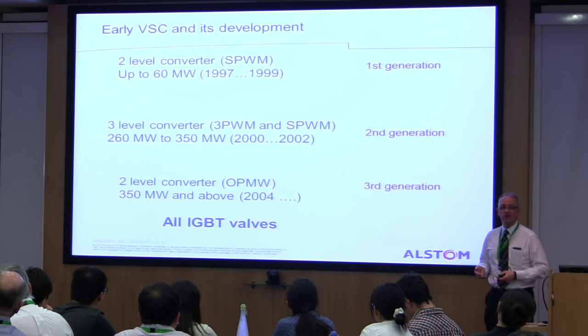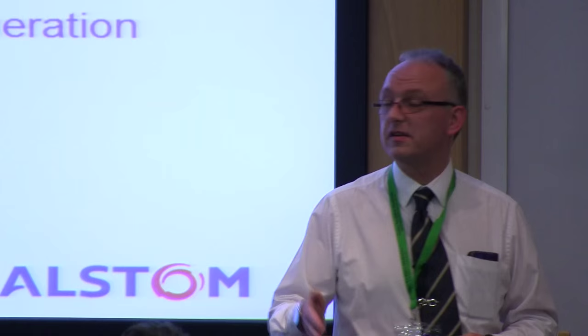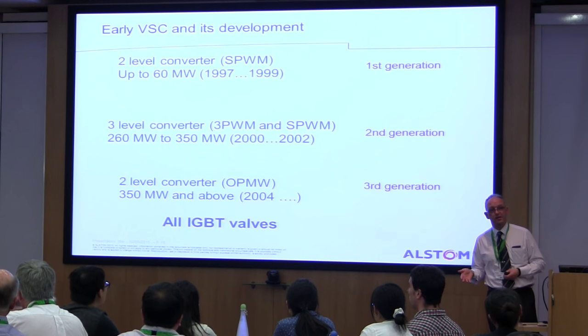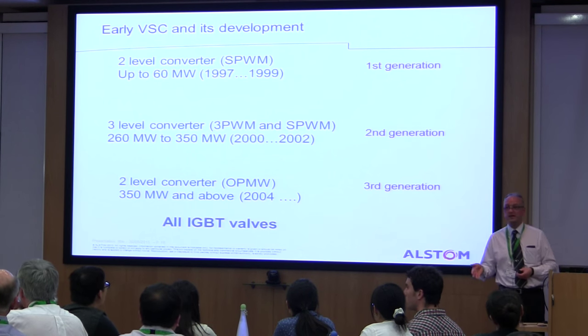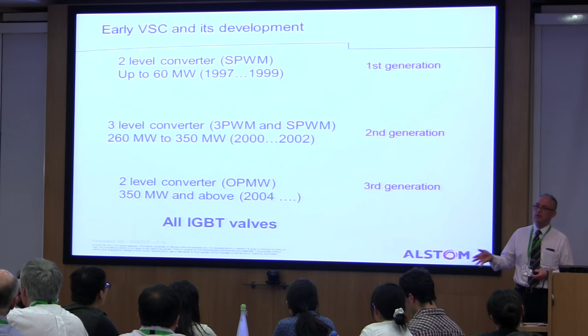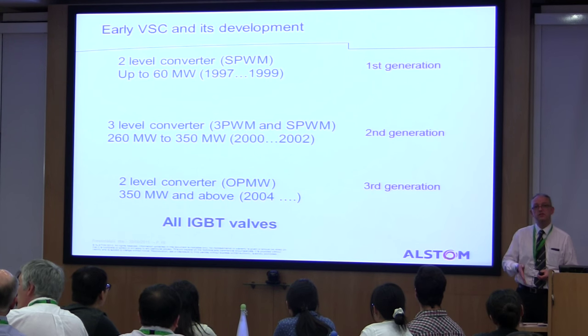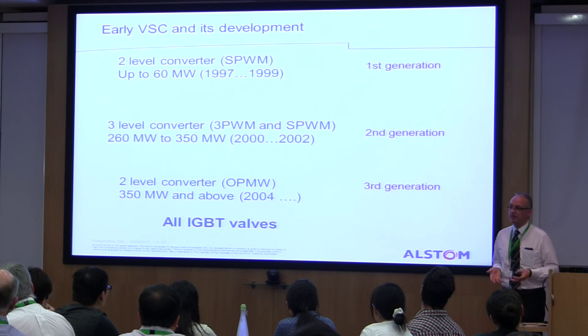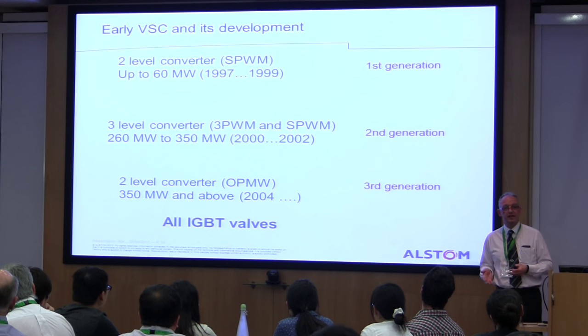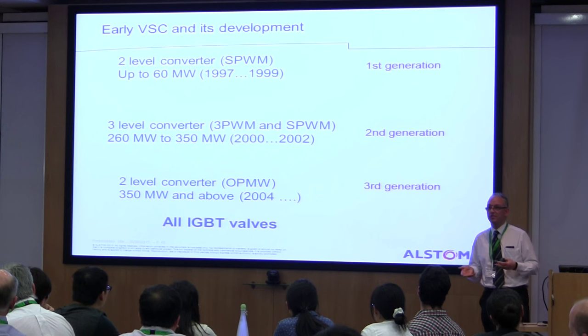The three-level converter dropped out of favour because of control complexity and we went back to two-level converters — but using optimal pulse width modulation, which means using a lower switching frequency to reduce switching losses, while accepting that you generate some harmonics into the power system and using passive filtering to remove them.